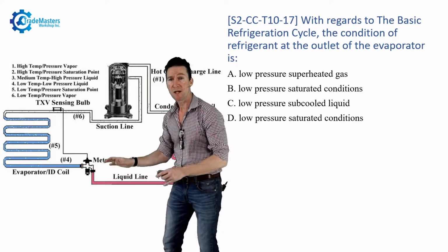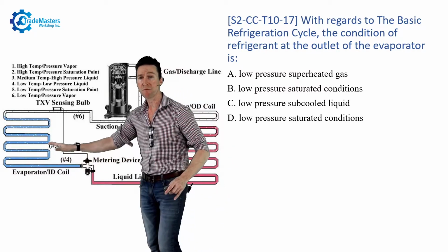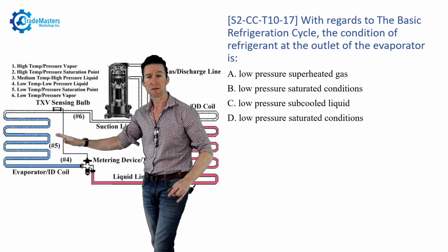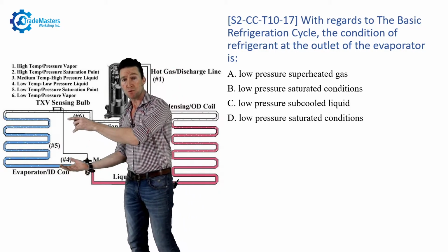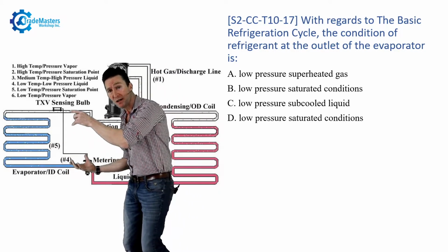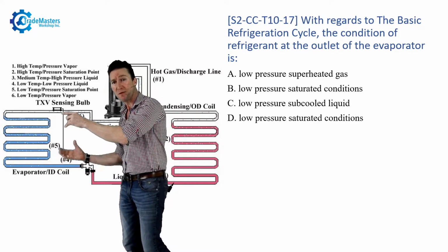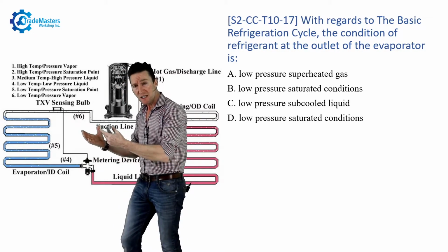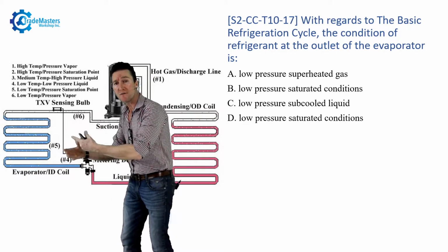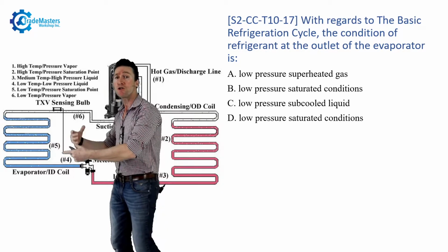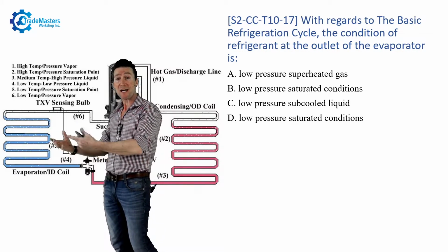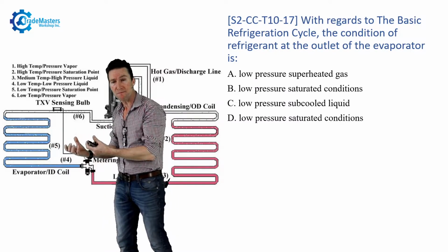and temperature drop to begin the boiling process of the refrigerant at a low pressure and low temperature inside the evaporator. If the evaporator is working correctly, it will absorb tons of latent heat from the medium to be cooled, which is blowing across the evaporator coil. If it's working correctly, all of the liquid fed into the evaporator should be boiled off to a vapor. This allows the evaporator to have a maximum capacity for heat absorption.